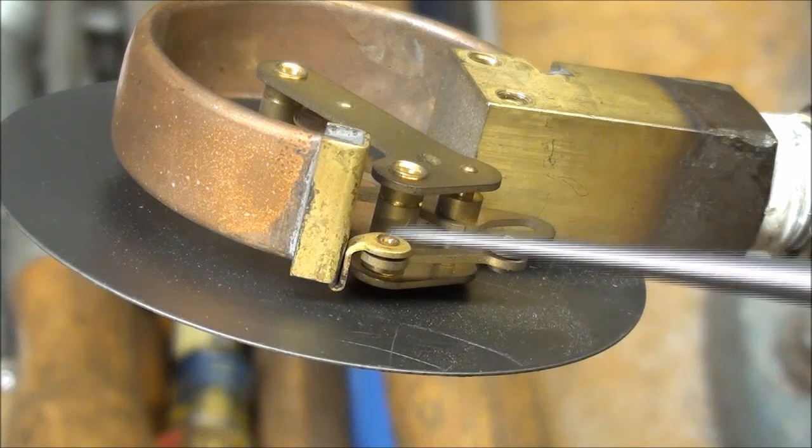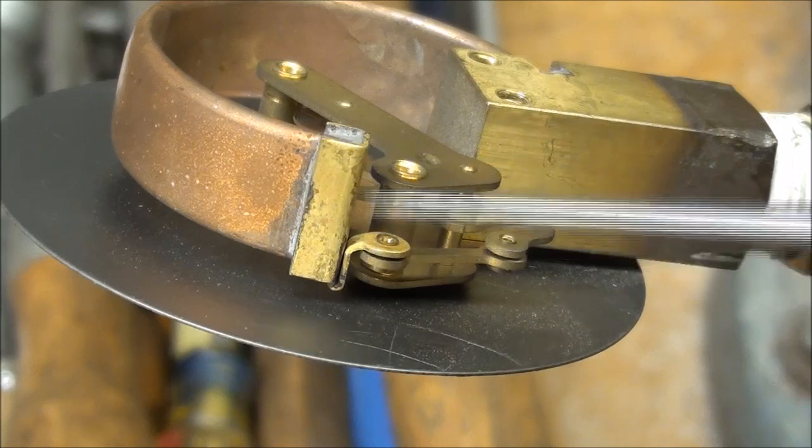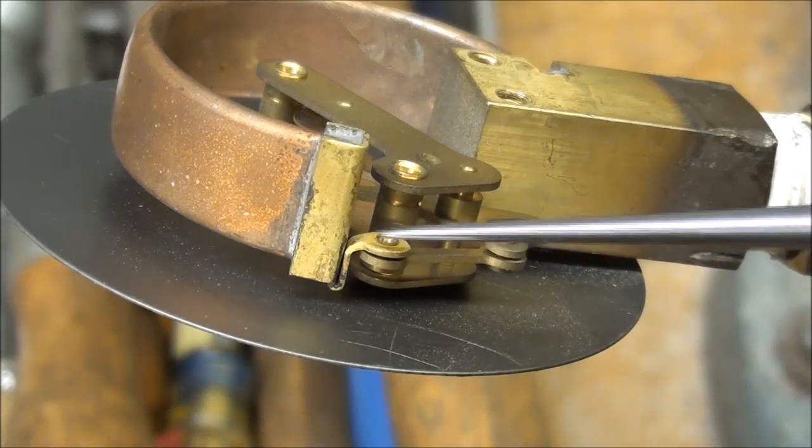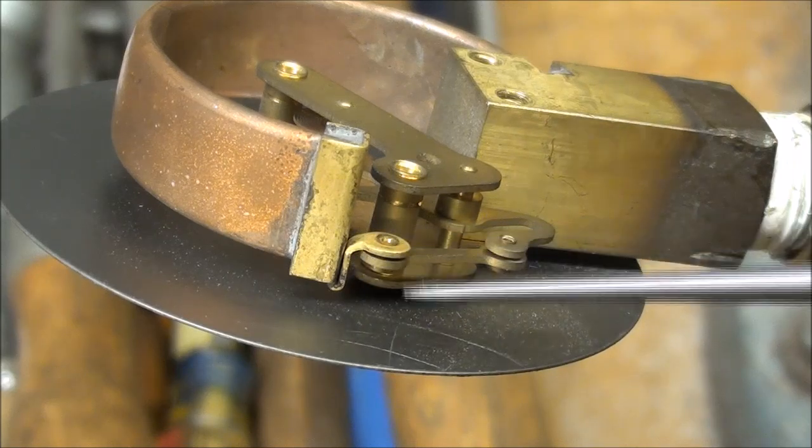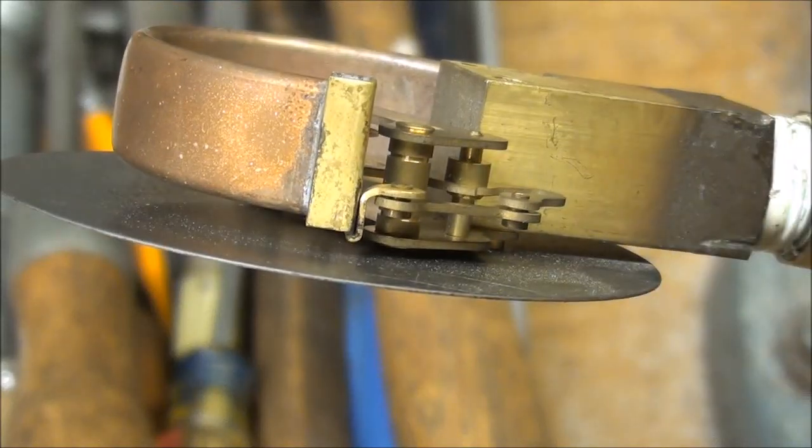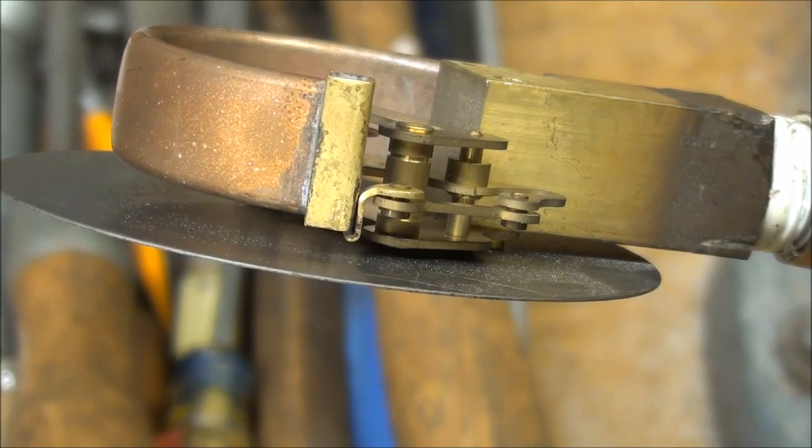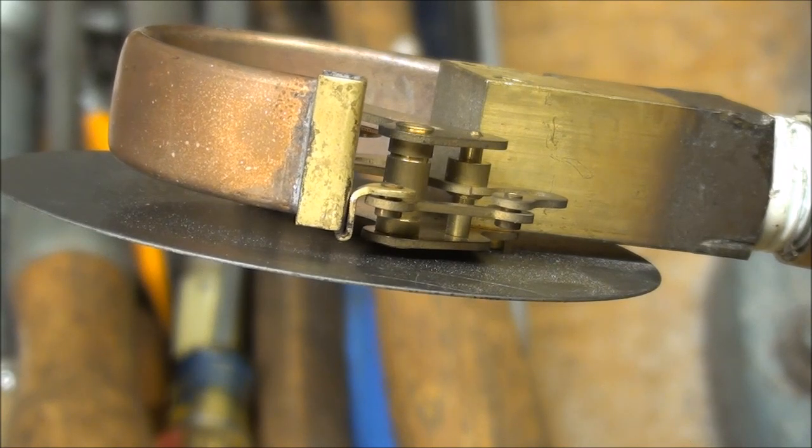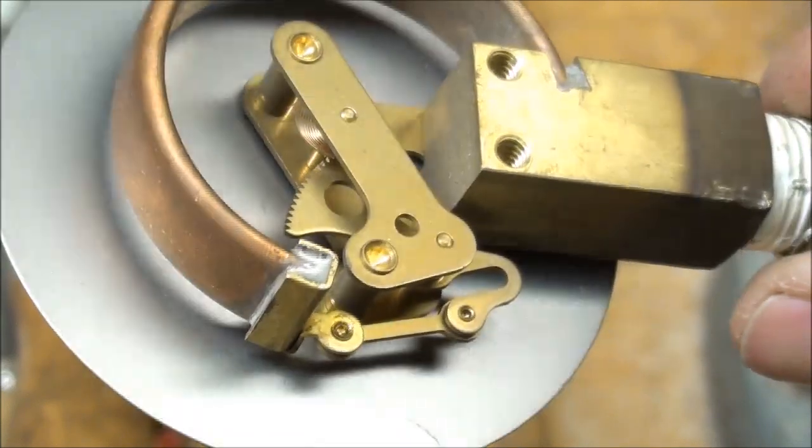From this view you can see this small link here is fastened on to the end of the Bourdon tube, permanently fastened, and then there's a pin here and here, and then this link here links it all to the movement. So watch now again as I pressurize it again, and you can see what the linkage is doing. Here comes the pressure. So that motion is transmitted through the linkages, and into the quadrant, and into the pinion, which in turn moves the needle, and I'll show you another view of that.